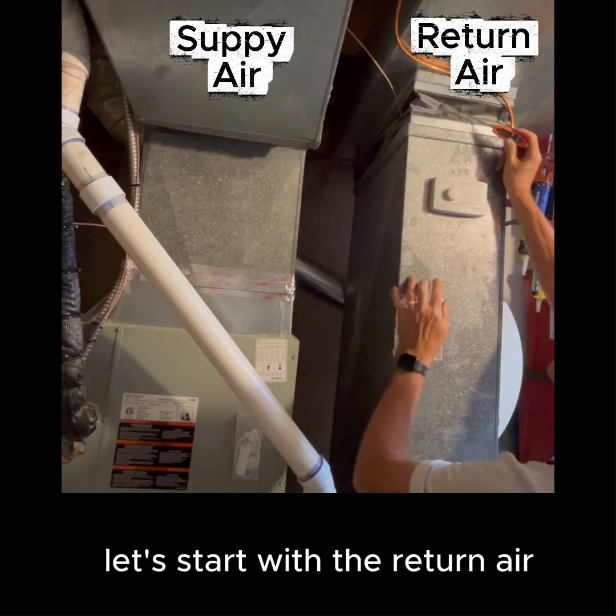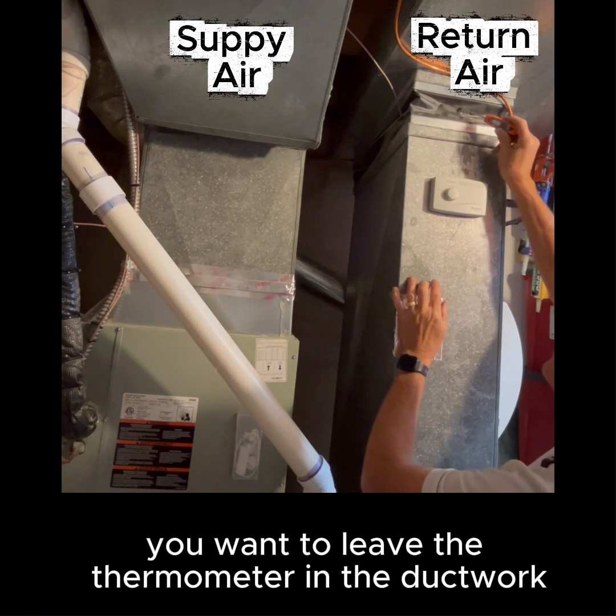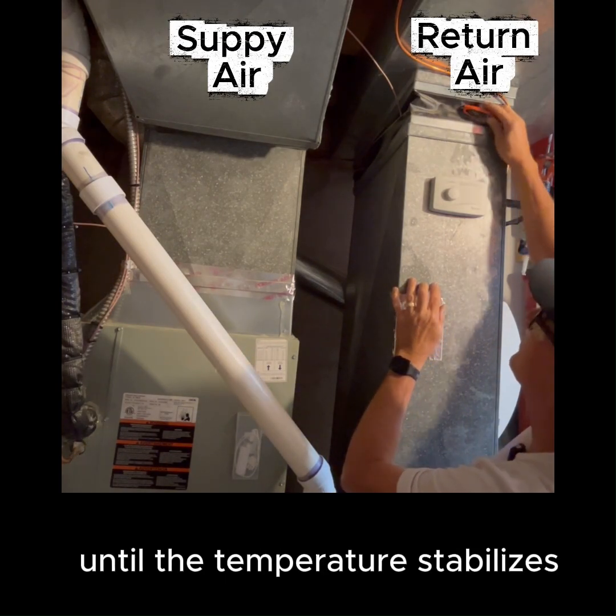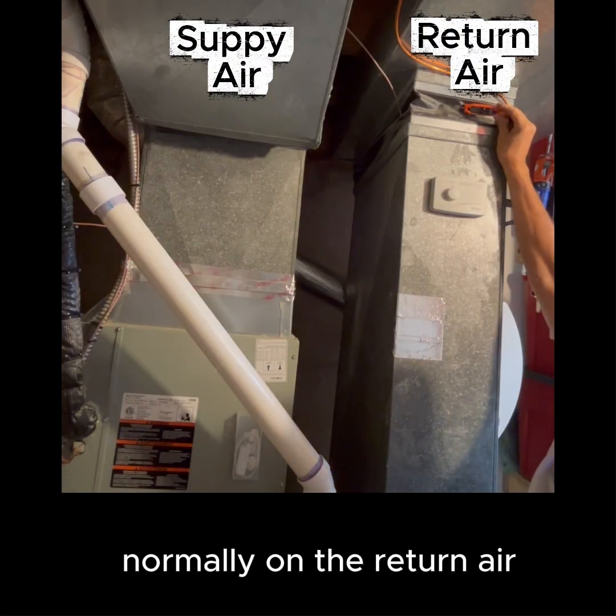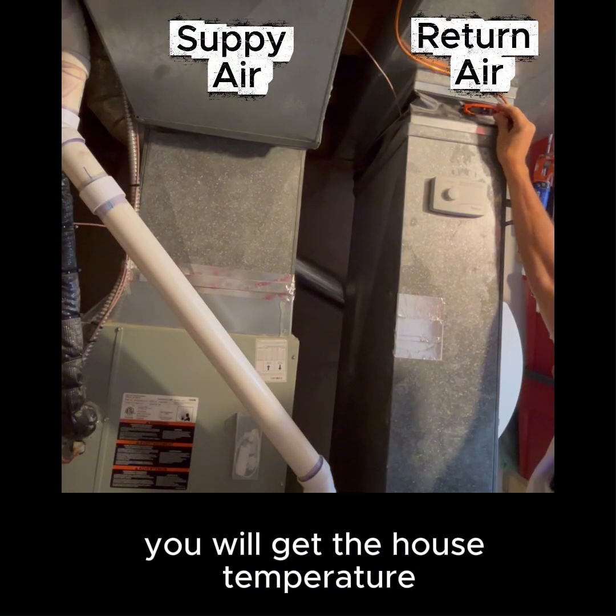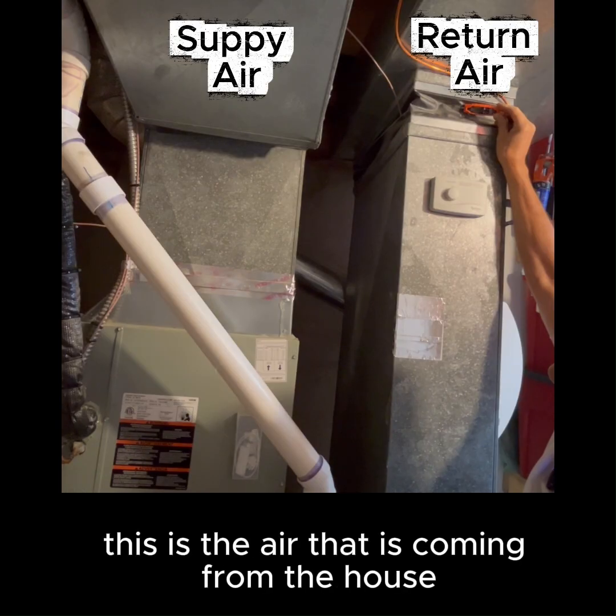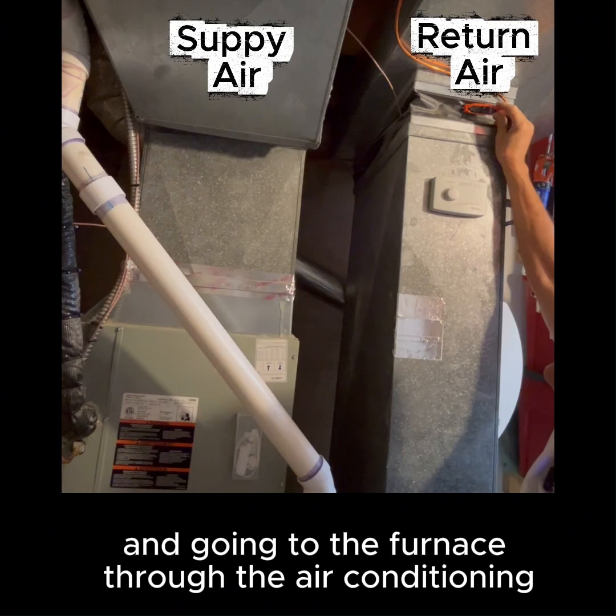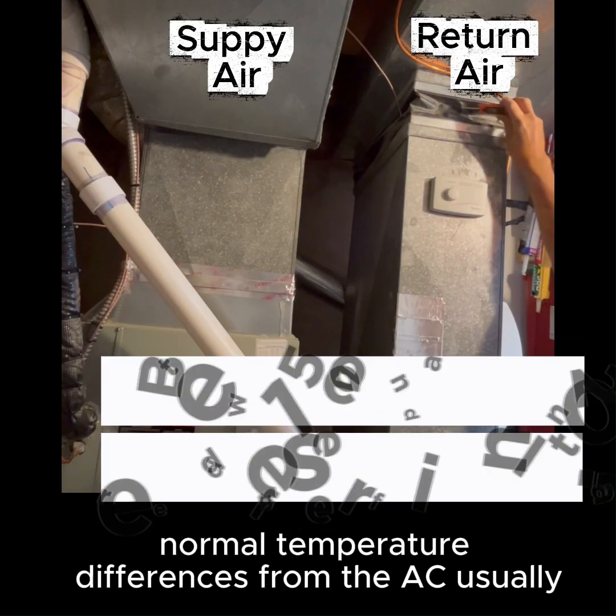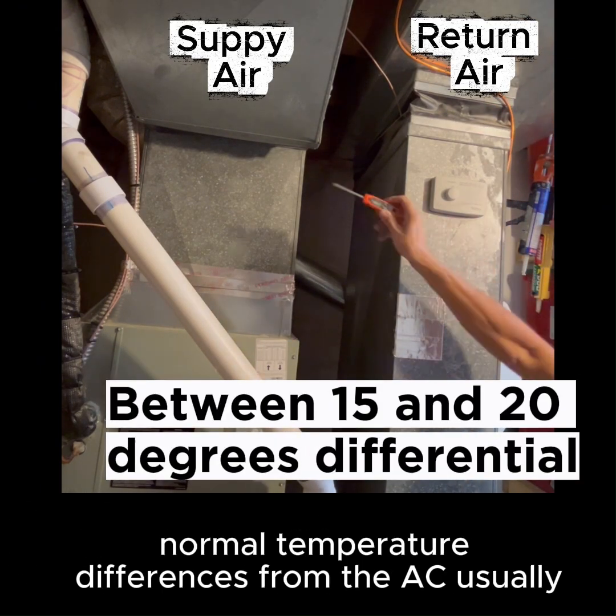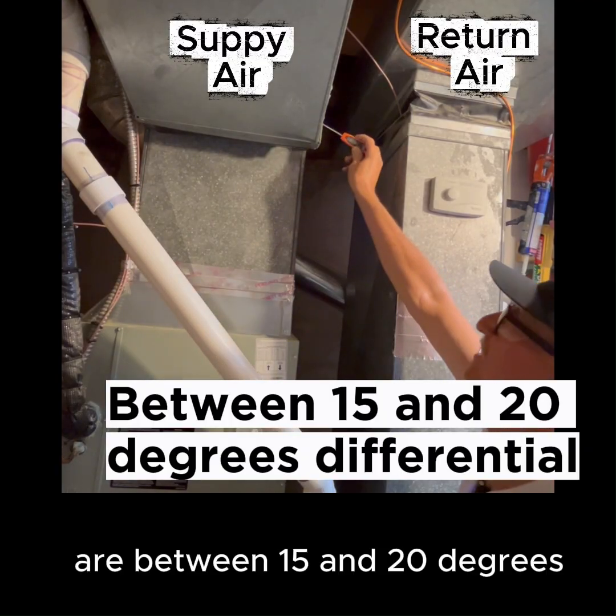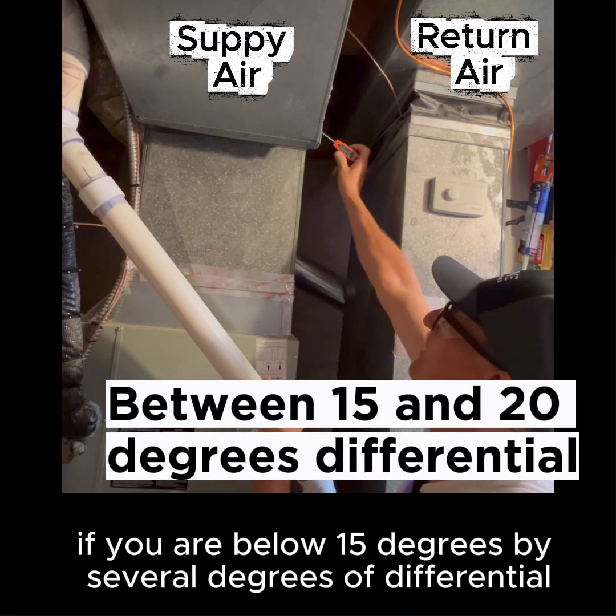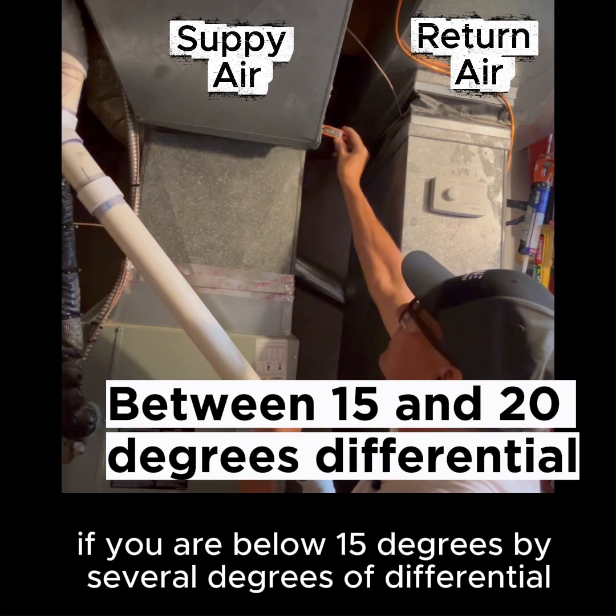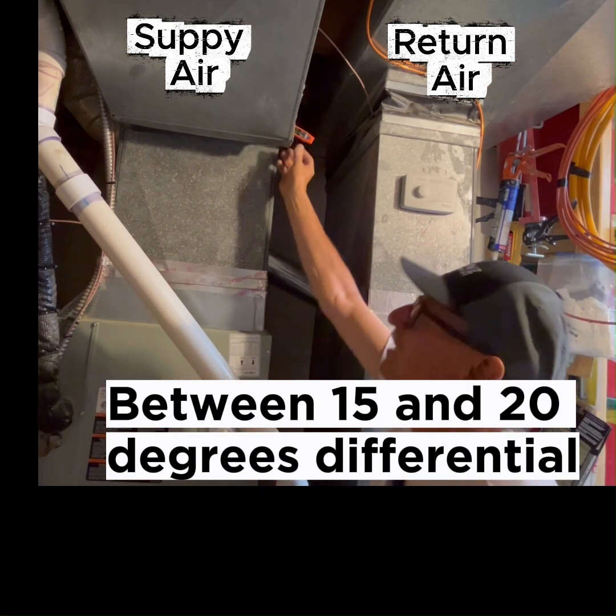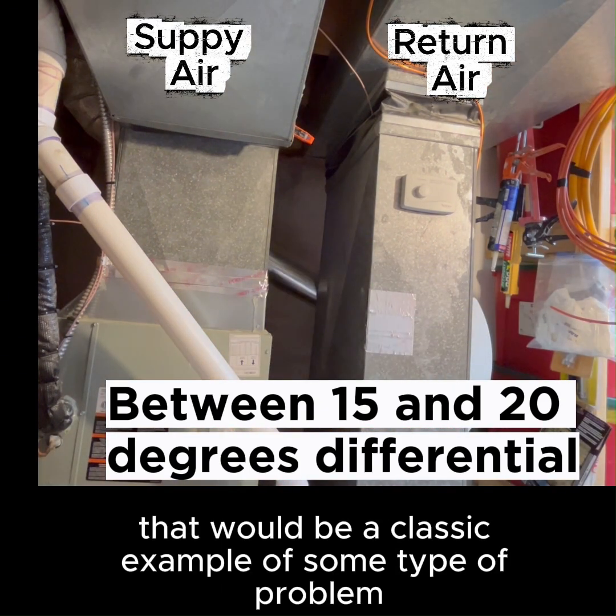Let's start with the return air. You want to leave the thermometer in the ductwork until the temperature stabilizes. Normally, on the return air, you will get the house temperature. This is the air that is coming from the house and going to the furnace through the air conditioning. Normal temperature differences from the AC usually are between 15 and 20 degrees. If you are below 15 degrees by several degrees of differential, that would be a classic example of some type of problem.